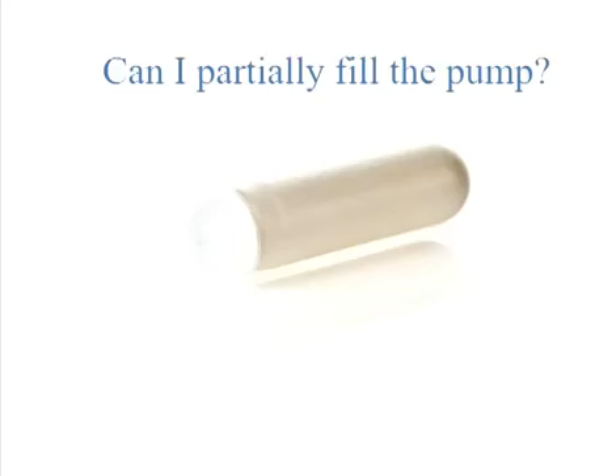A common question we get is, can I partially fill my pump? If I have a 2-week pump but fill it halfway or 50%, does that mean a 1-week infusion? Let's imagine that this pump is 50% full, and that means that 50% of it is air. And remember that the pump is a continuous delivery device. It'll administer everything that's inside of it continuously. Now, in the case of a half-filled pump, it will sometimes administer your test solution and sometimes administer the air. This will not result in a continuous delivery of your drug, and for this reason, the pump cannot be partially filled.